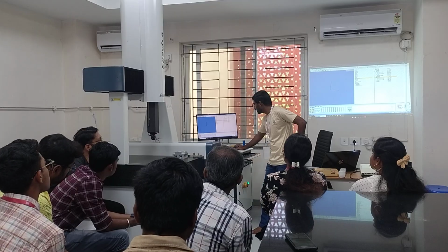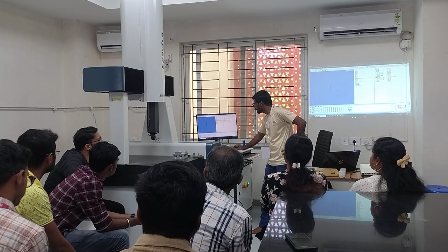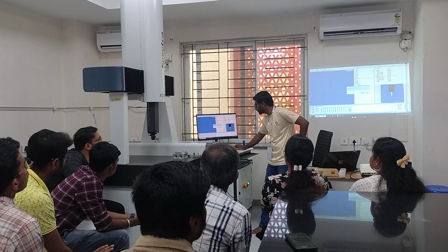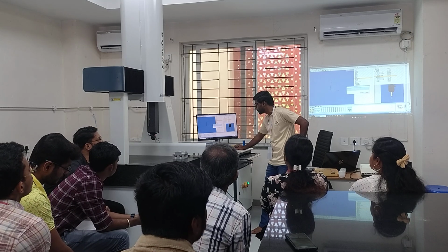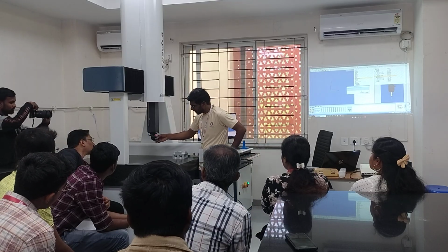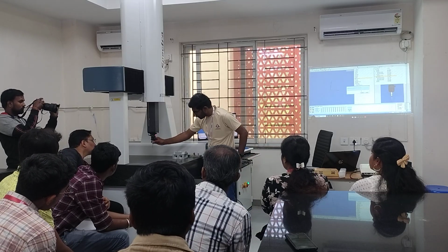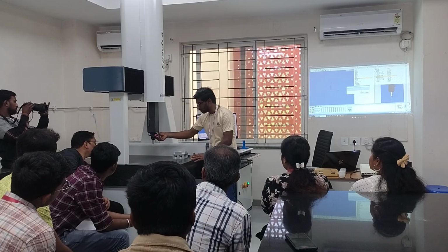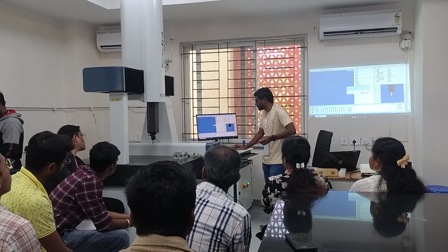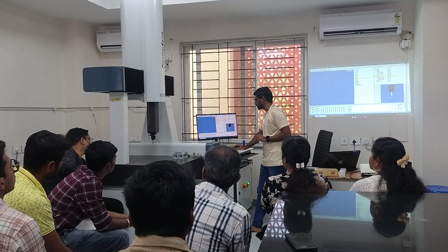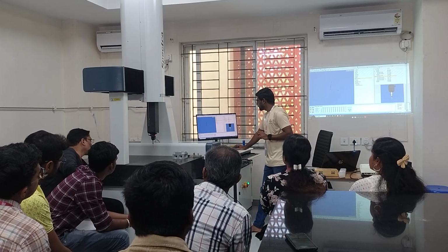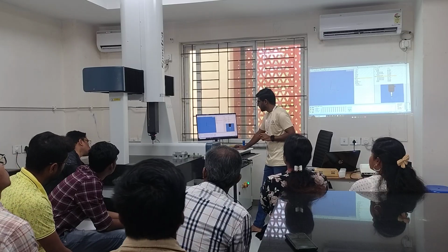Currently I see that A0, B90 is activated. If I right click here and activate, it means 0, 0 is getting activated. It is telling me please rotate the sensor into A0, B0. Okay, I just loosen it. B0 is already there. I loosen it to A0 and I have locked it. So now A0, B0, I have to rotate and I have done it. Then it's telling something, no. So it is already accepting it. So this activation, deactivation can be done.